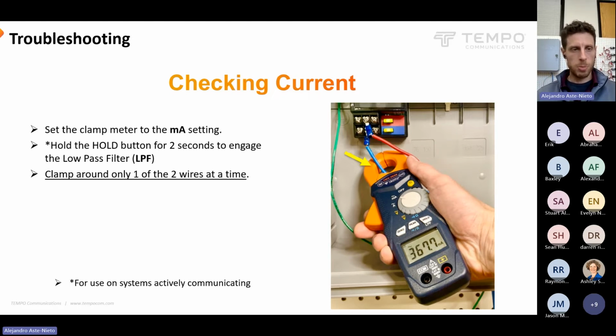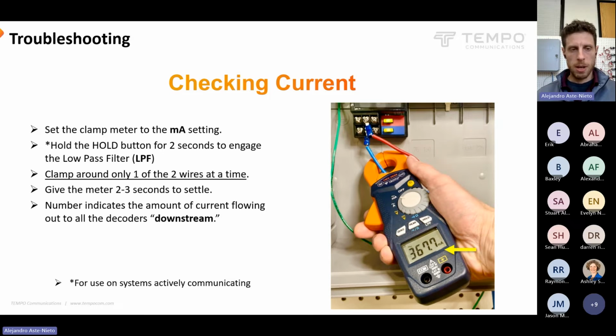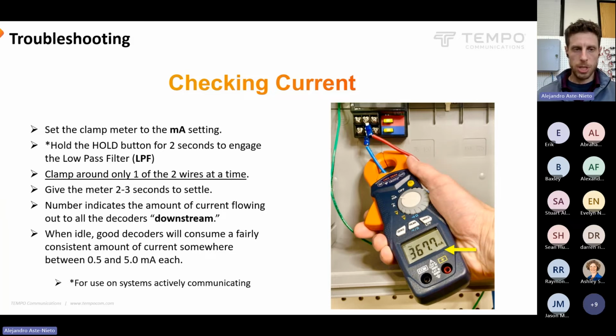So you'll actually see a non-zero number if you're clamped around both wires in that situation. But for the most part, what we want to do is clamp around one wire at a time when we're taking measurements. Once we clamp around, give it 2 or 3 seconds, and you'll start to see a steady number. That number indicates the amount of current flowing out to any downstream decoders. So again, when idle, those decoders are going to consume the consistent amount that they're supposed to be consuming, somewhere between 0.5 milliamp and 5 milliamps. But you're going to want a more specific number for whatever system you're working with.